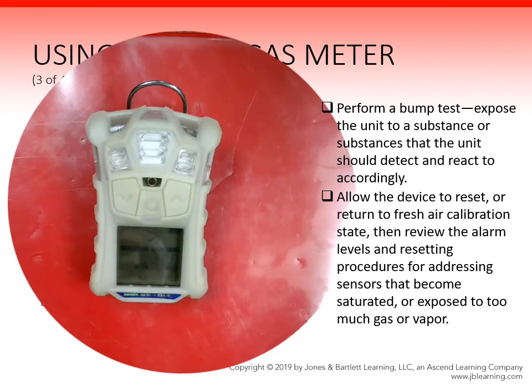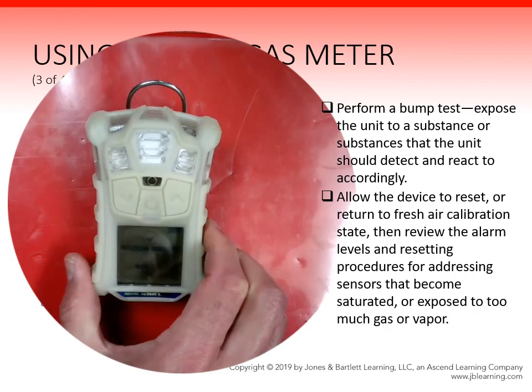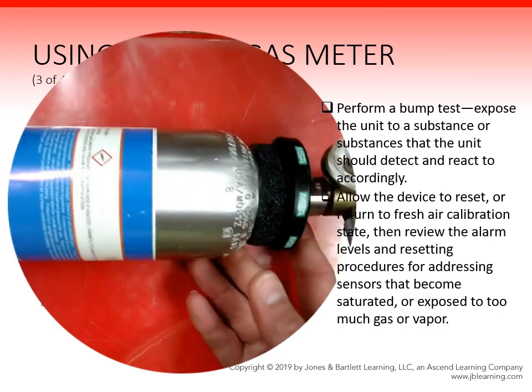Now what we're going to do next is perform a bump test on this meter. A bump test, once again, is a field test that simply confirms the sensors are able to detect the gases that we are monitoring. It doesn't necessarily give you an indication that the sensors are accurately reading those. That's what calibration is for, and we do that once a month. The bump test is a daily check just to make sure the sensors are still operating as we would expect them to operate. So in order to do that bump test, we're going to use a canister of gas.